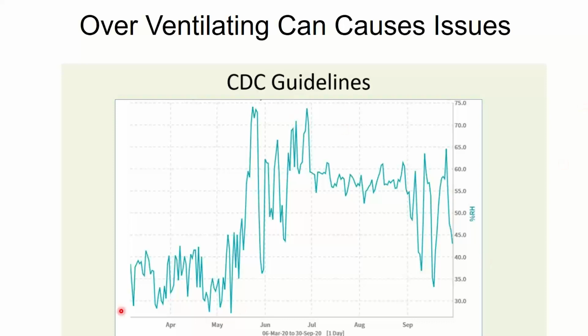In this example, this particular building was bringing in the code required amount of ventilation air, and then they jacked it up, doubled or tripled it or something, because of COVID. You can see what happened to their indoor humidity. Things were nice and in check around 30 to 40%. Then we get to June, and the next day when they turned it on, humidity jumped up into the 60s. So just be careful with that.